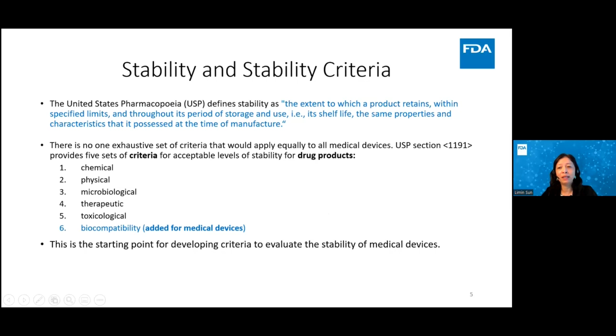There is no one exhaustive set of criteria that would apply equally to all medical devices. USP does provide 5 sets of criteria for acceptable levels of stability for drug products. These are chemical, physical, microbiological, therapeutic, and toxicological. Although this set of criteria applies specifically to the evaluation of drug product stability, it is useful as a starting point for developing criteria to evaluate the stability of a medical device. Please note that we do add biocompatibility for the medical device.